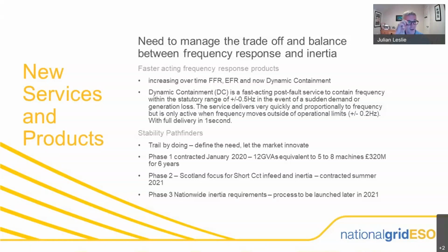So as you can imagine, as the inertia falls on the system and the frequency is falling, we've got about 1,000 megawatts of this really, really fast frequency response now. So we get 1,000 megawatts injected into the network within a second, which then arrests the fall in frequency. Then our other frequency response products kick in and return the frequency to the operating standards. So dynamic containment has been a huge success and is now allowing us to operate the grid in a way that I never thought possible even 18 months ago. Because it acts so quickly, you can run the system at very, very low inertia levels.